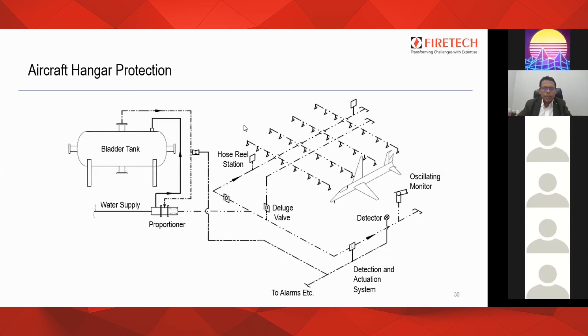The operation philosophy: in case of a fire detected by the UVIR detectors, they send a signal to the alarm panel. The alarm panel then activates the deluge valve at the inlet of the foam proportioner. Deluge valves are also provided downstream for individual systems — the foam sprinkler has one deluge valve, the hose reel station has one, and the oscillating monitor has one. These deluge valves can be programmed to operate simultaneously so the whole aircraft hangar can be flooded with foam.